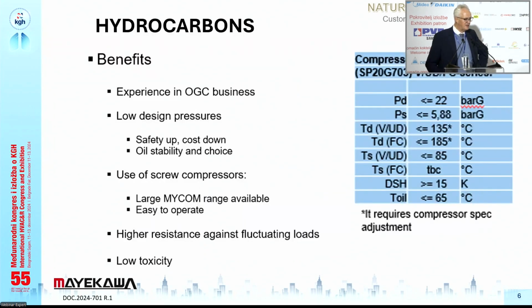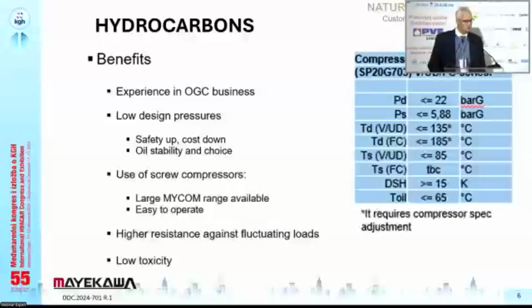Now, speaking about the hydrocarbons, of course the benefit of the hydrocarbons is that we have really experience in the oil and gas compressor business, with which we are busy 60 years. And not only we, I speak also for our colleagues. The pressures, they are lower compared with ammonia. So it is safety up and cost down. And the oil stability and the choice, of course, is another benefit. The use of screw compressors, of course, there are large MYCOM ranges of screw compressors available, and they are easy to operate the compressor on itself. Then we have higher resistance against fluctuating loads, and we have low toxicity, lower than ammonia.